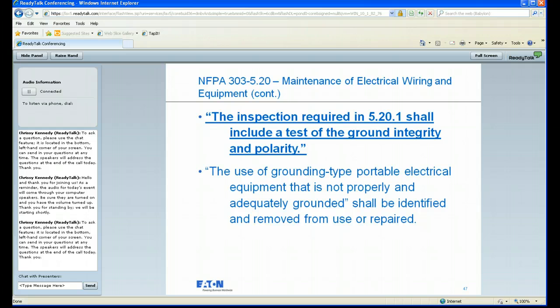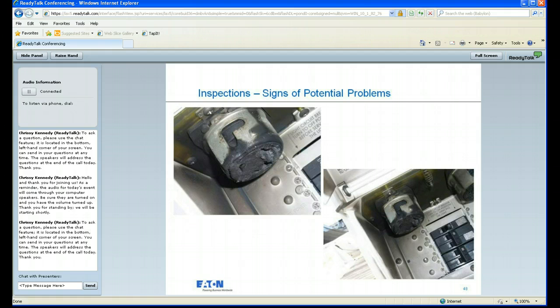The big portion of this code requires that the ground integrity or polarity of your grounding system needs to be checked as well. That's the big issue. The ground is probably the most important piece of equipment you're going to have in your system, and making sure that it's working properly is very important. The bottom statement there: if you find any grounding type of portable electrical equipment that is not working properly and adequately grounded, it needs to be removed or repaired immediately.